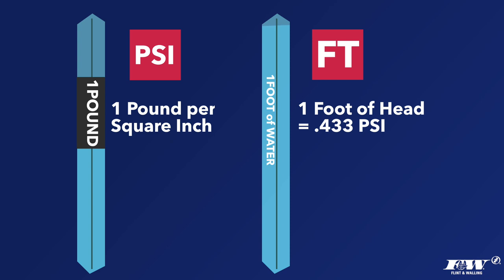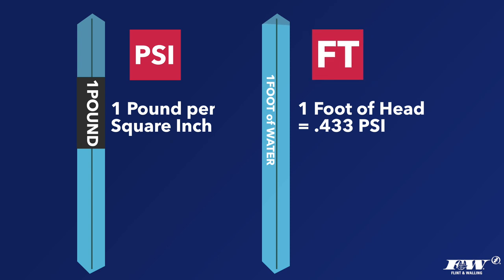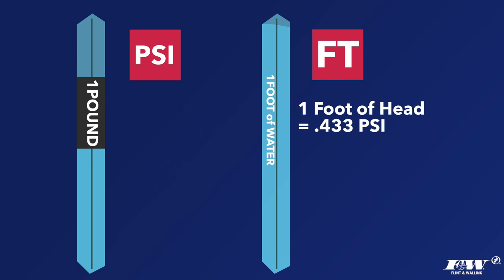We use both units because sometimes it's easier to calculate in feet of head and sometimes in PSI. We can convert between them based on the weight of water: since a one-foot-tall, one-square-inch column of water weighs 0.433 pounds, one foot of head equals 0.433 PSI. Conversely, dividing one pound by the weight of that column tells us that one PSI equals 2.31 feet of head. The great thing about feet of head is that the vertical distance between two points in the irrigation system in feet equals the pressure difference between those points expressed in feet of head.